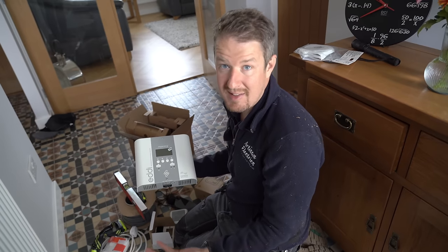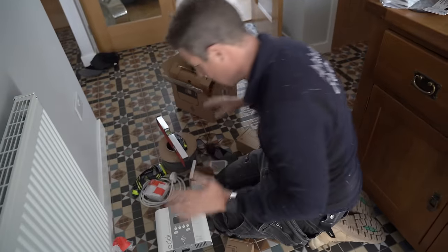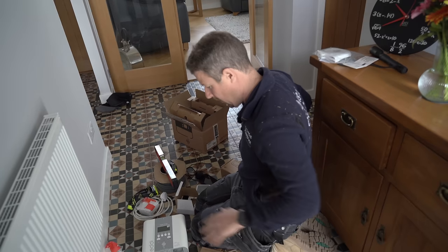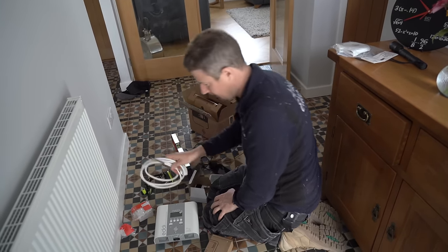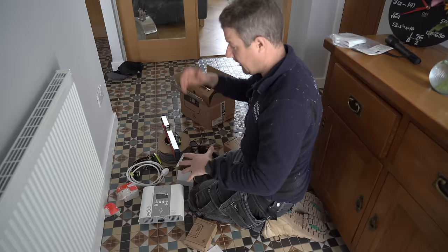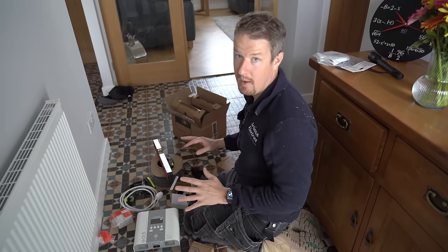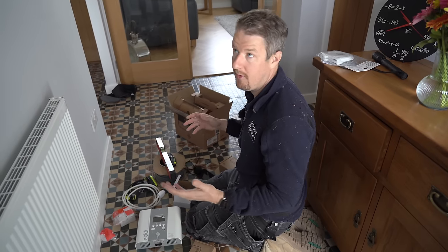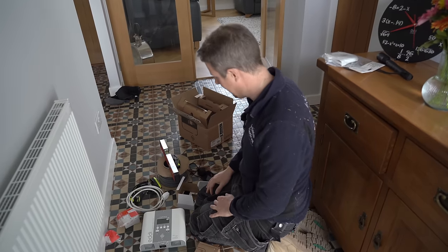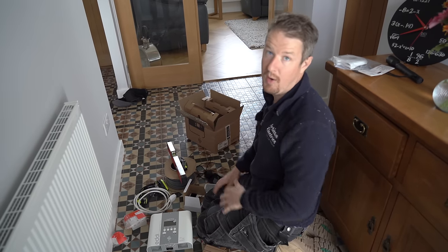It's called a micro-generation energy diverter because it diverts excess energy into heating your hot water, essentially turning your hot water tank into a heat battery to store that energy as hot water. We tend to connect it up on a plug first because we've had teething problems in the past with firmware updates. We pair it up with the hub and Harvi, connect to the internet, get all firmware updates done first — there's nothing worse than getting it fully installed and then finding connection issues.